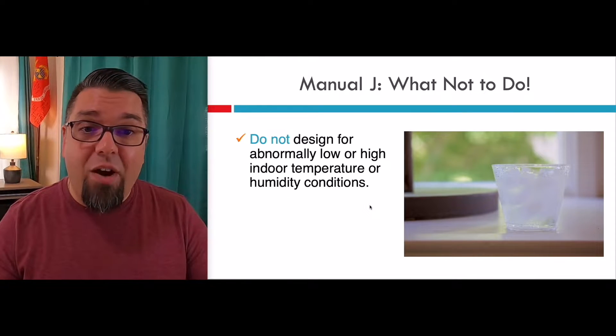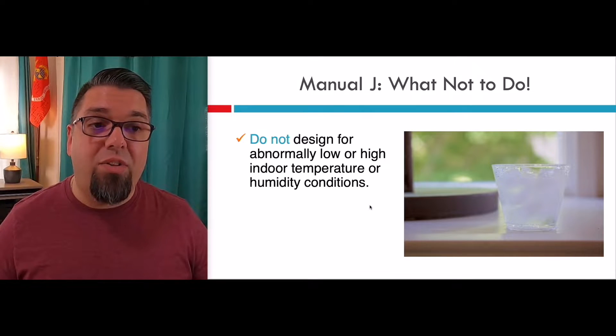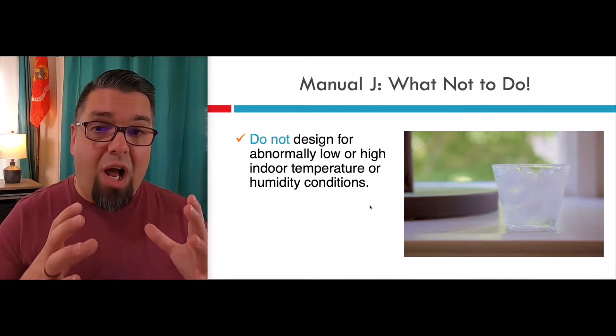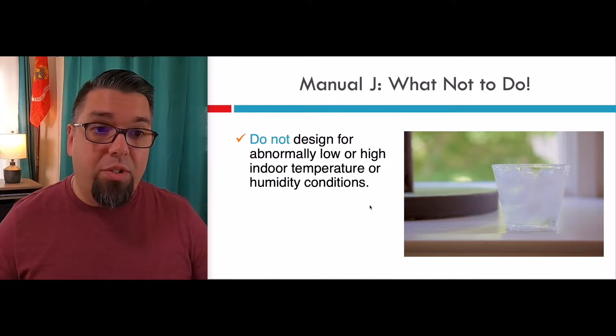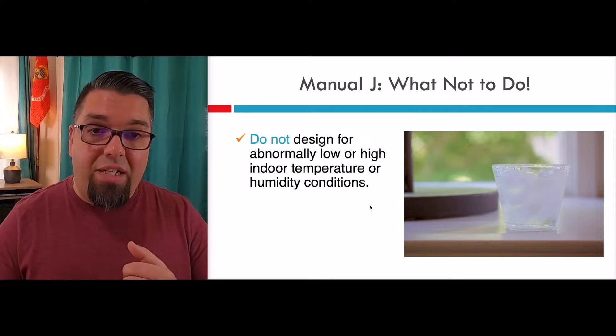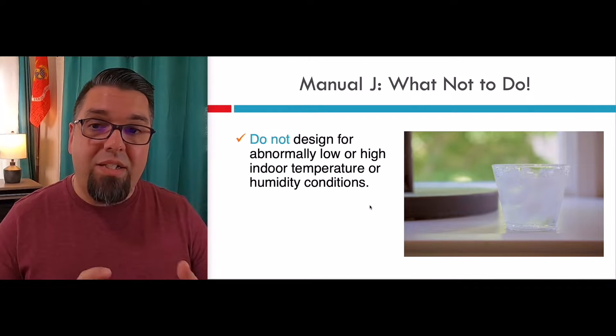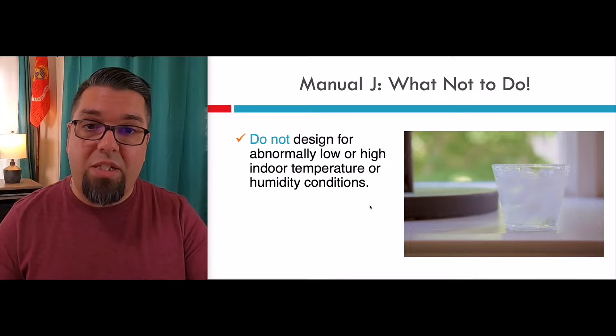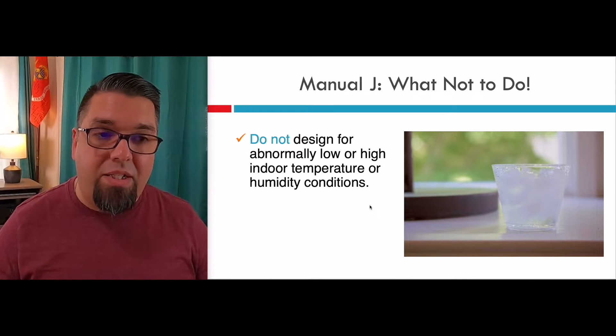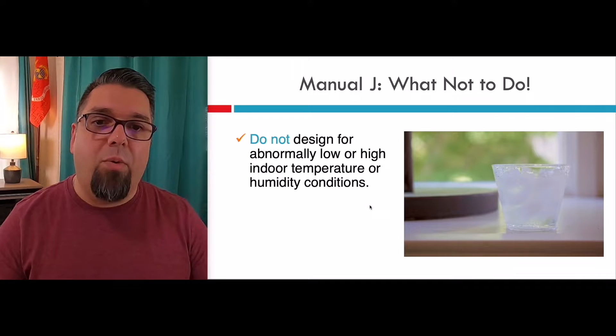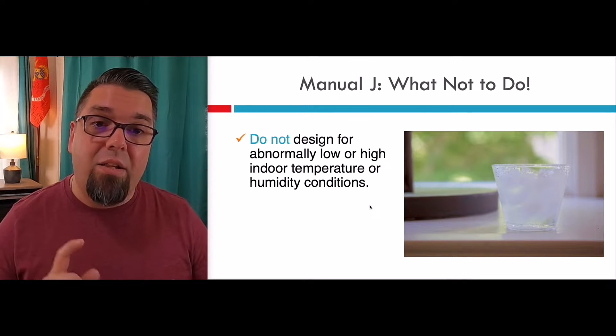Also, don't design around abnormally low or high indoor design temperatures or humidity conditions. This is the number one reason I see mold in homes — high moisture content migrates through walls, windows, and cracks, creating mold. Your design temperatures need to match the mechanical code and the IRC. In cooling: 75 degrees and 50% relative humidity. In heating: 70 degrees plus or minus 2 degrees — as low as 68, as high as 72. Design around normal conditions as prescribed by the IECC, the mechanical code, and the residential code.